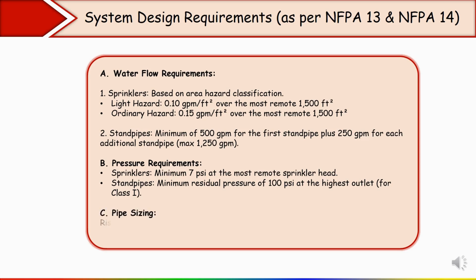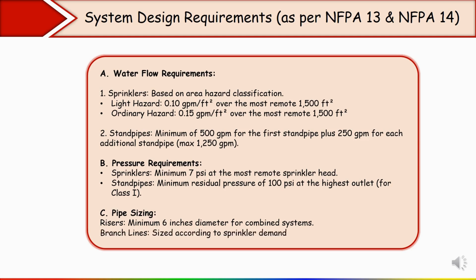Now next thing is pipe sizing. Remember, when you are sizing the riser pipe for combined system, it should be minimum 6 inches diameter. Pipe size totally depends on the sprinkler pipe size and standpipe, which we will discuss in hydraulic calculation, and I have also discussed in the previous lecture. Here the requirement is that for the combined system, the riser, the vertical pipe running throughout the building, should have a minimum diameter of 6 inch, correct? And for branch line, size according to sprinkler demand. Clear?